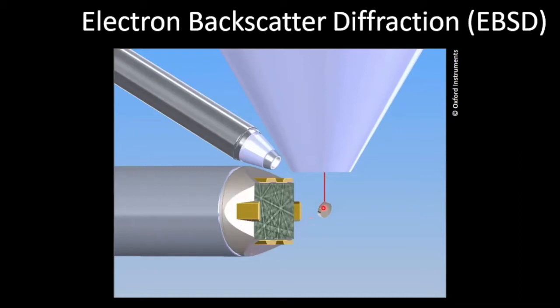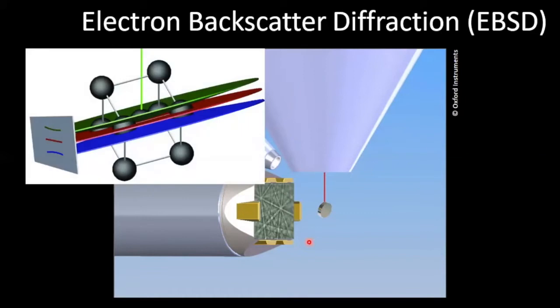The EBSD detector comes in perpendicular to the beam, so you actually have to angle your specimen at about 70 degrees in order to get an optimum signal on your EBSD detector. What that means is that the angle at which your beam is interacting with the different atoms within a structure changes, and we can actually detect that — we're talking about an electron beam interacting with the structure.